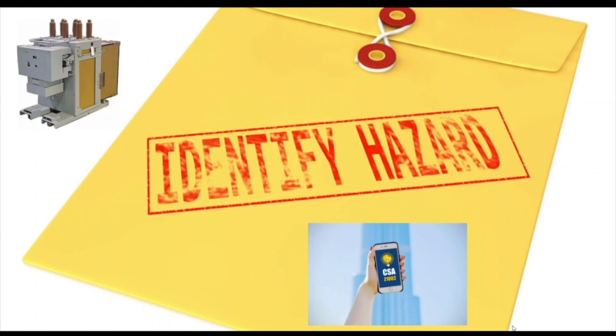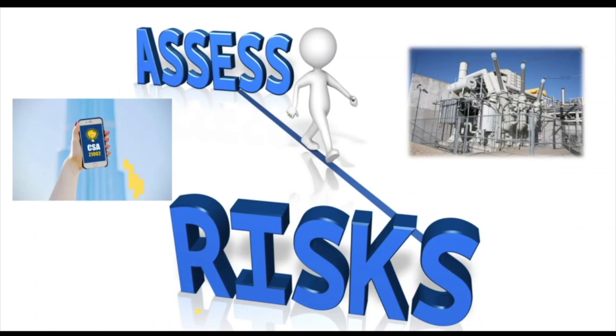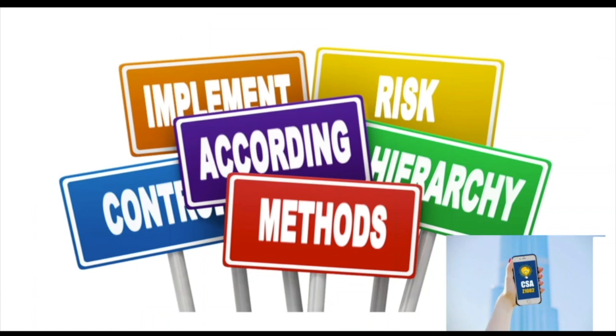The steps: identify the hazards. That's something you really need to do, and you need to do it at a high level. You need to assess the risks, and you need to implement risk control according to a hierarchy of methods. Those are the three steps right from Z1002, which we have embedded as a best practice based on our benchmarking in CSA Z462.